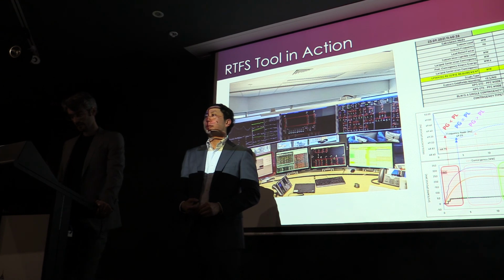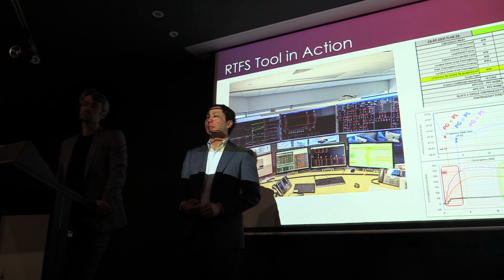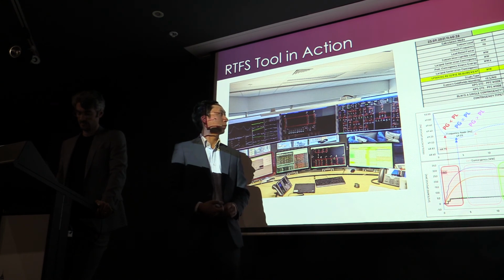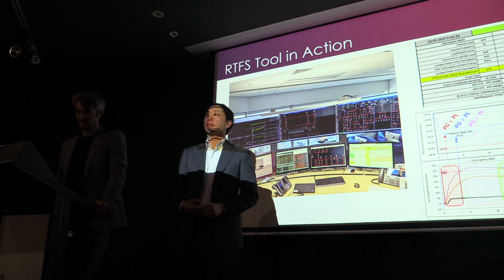So there were all these practical problems, but I wonder if some of them are being solved in one way by having more inverter-based technology, especially if we get some batteries, of course. We might actually have less of a problem with thermal units. I'm just looking at that spinning reserve: you've got 9 units on with 600 megawatts of headroom in their generation capacity. Do you need to do much if there's that much sitting there?